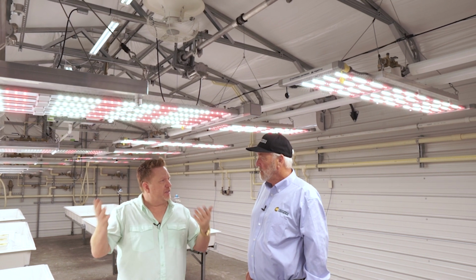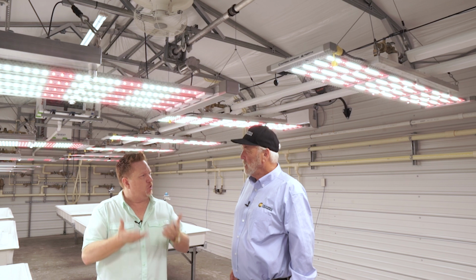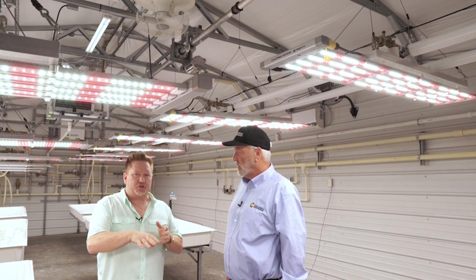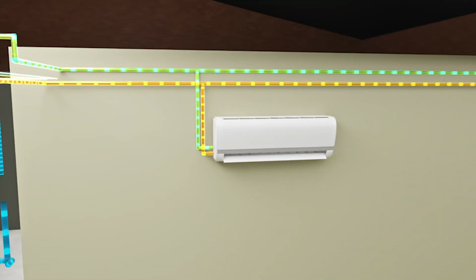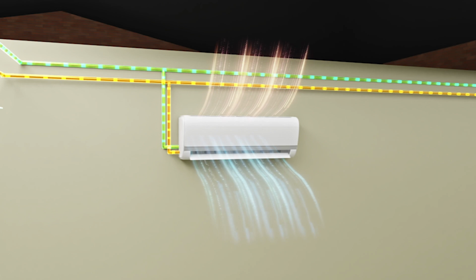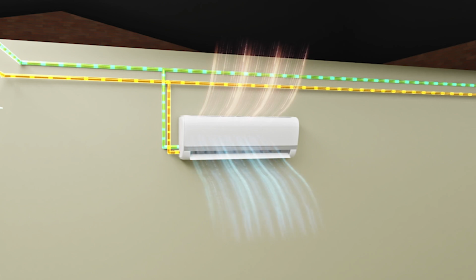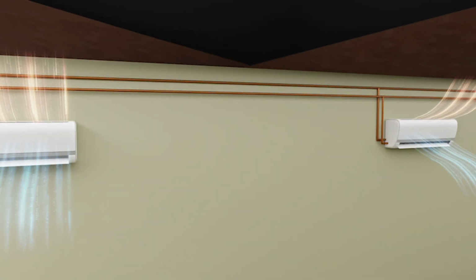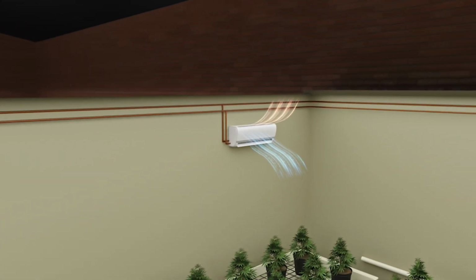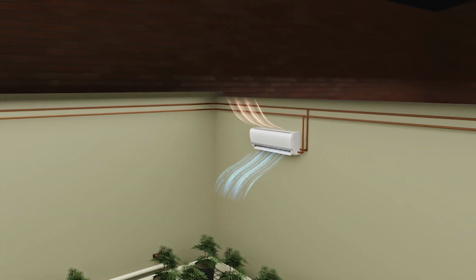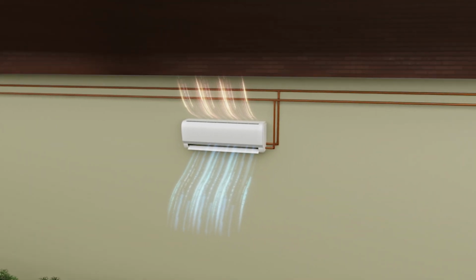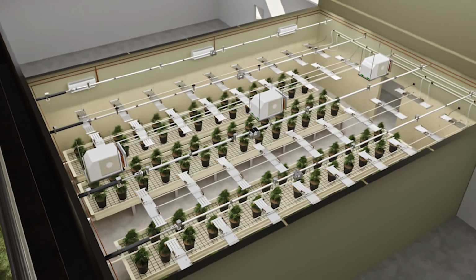When you really start that big canopy and that high humidity dump that the plants will discharge into the room, that's when the HVAC unit picks up, because then the dehumidifiers will be putting out more heat and the discharge will creep up to about 82, 83 degrees, right? And then the HVAC takes that out. So this whole room will operate on 3 tons of HVAC.